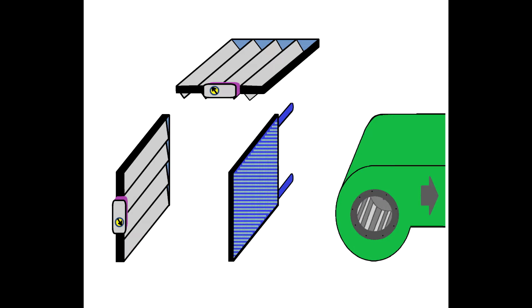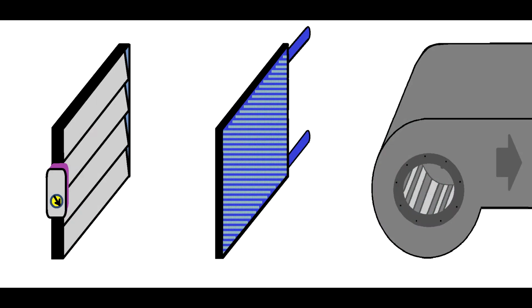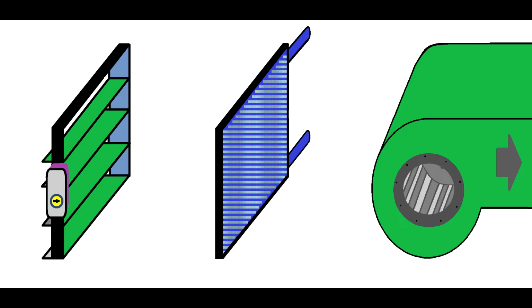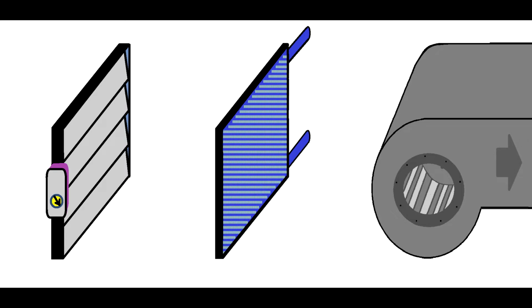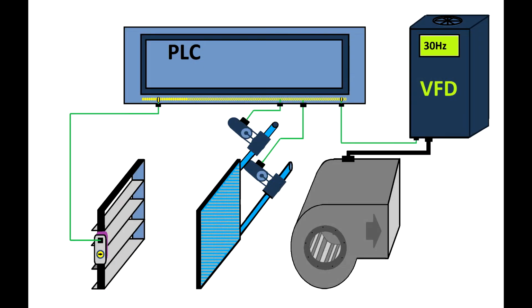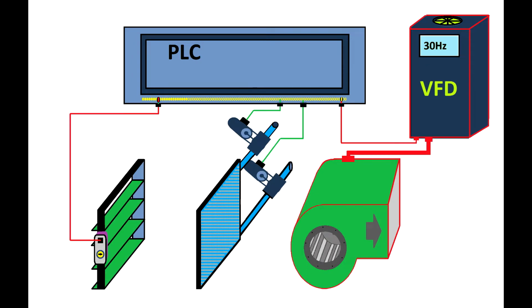They can be proportional. Like in this case, you see this fan will suck air either from the horizontal damper or from the vertical one. It's up to how you choose to control the airflow. In this particular case, the damper must be 100% open before the fan will be activated. Otherwise, the supply air chamber will act like a blocked vacuum cleaner. What you will see here is an integrated damper. So when the damper opens, we'll instruct the PLC to turn on the variable speed driver that controls the motor.